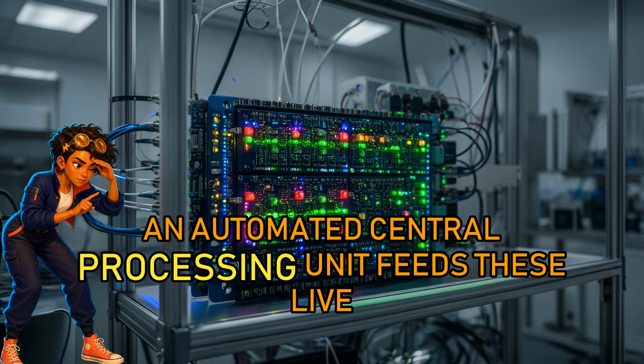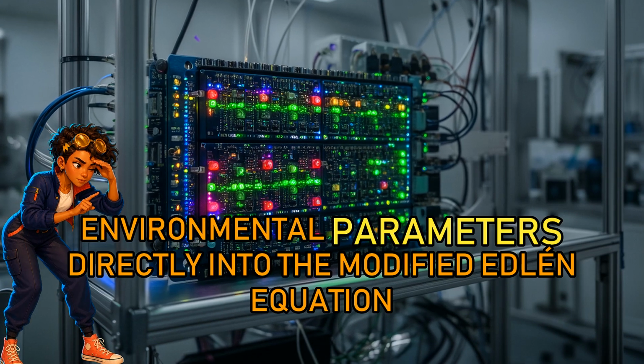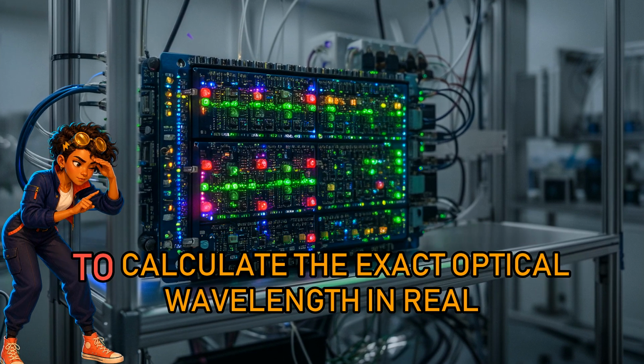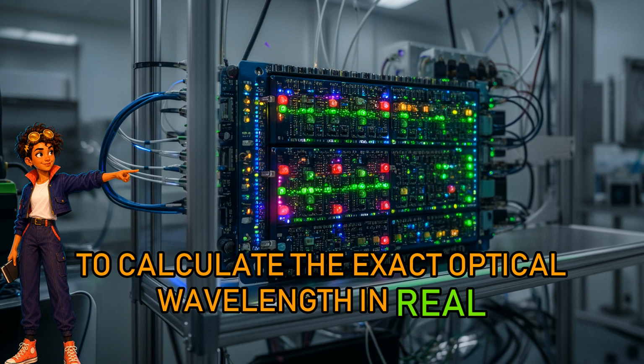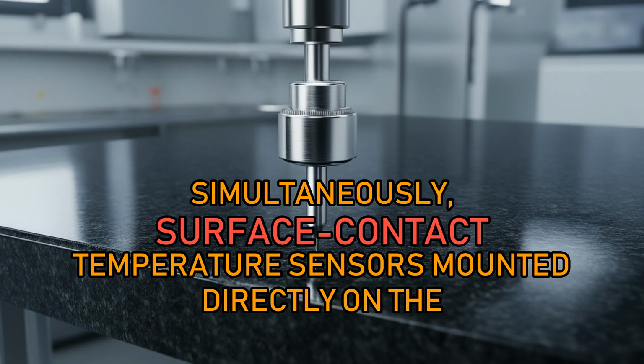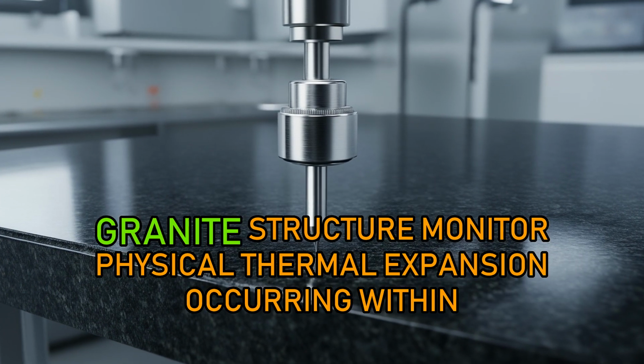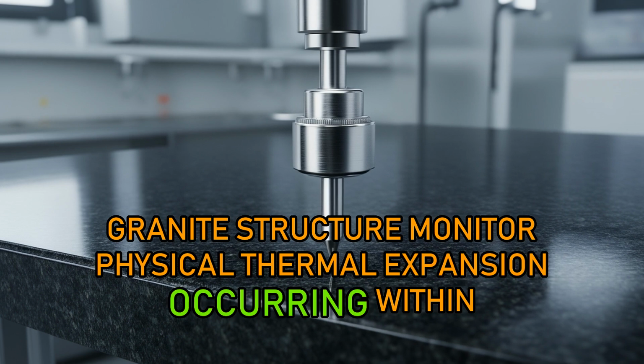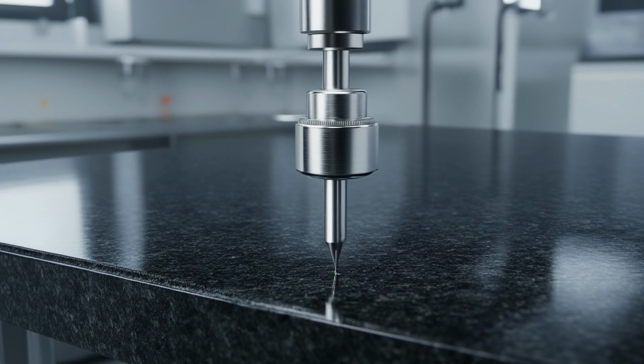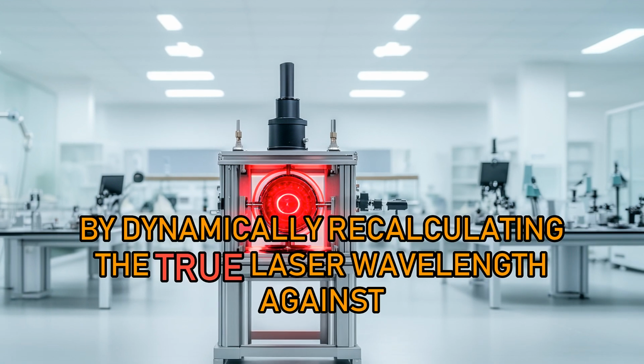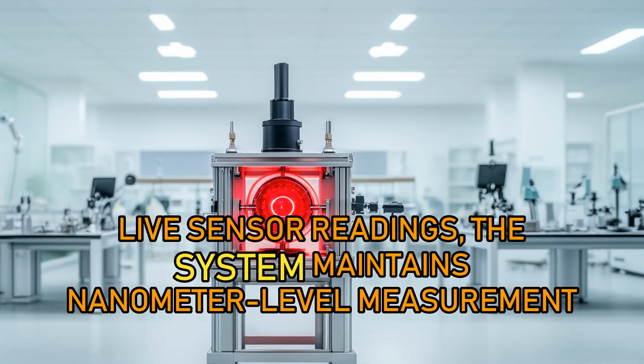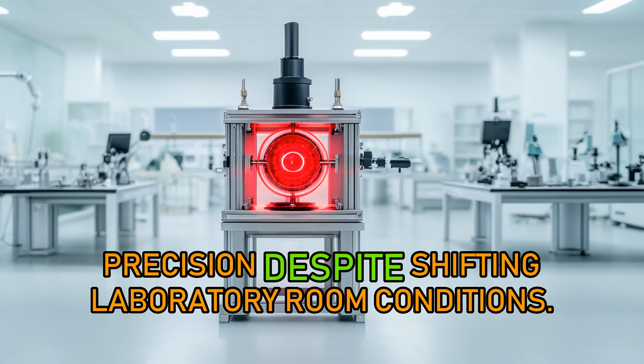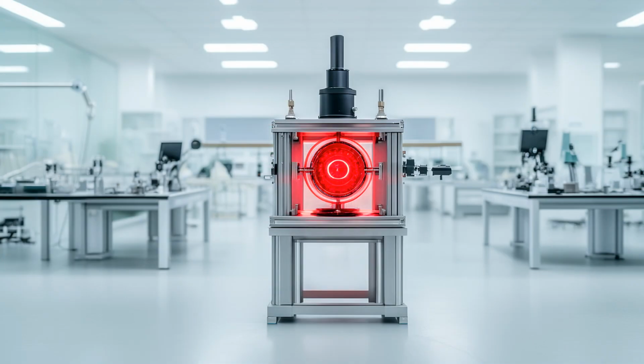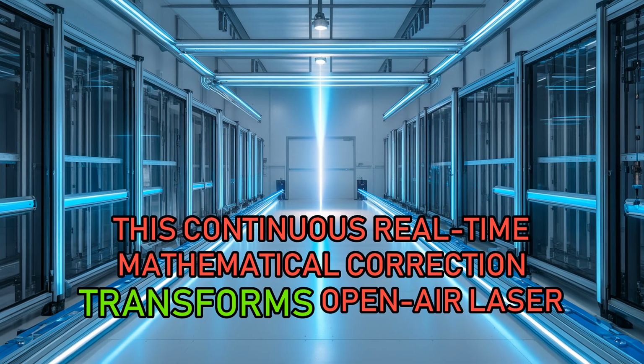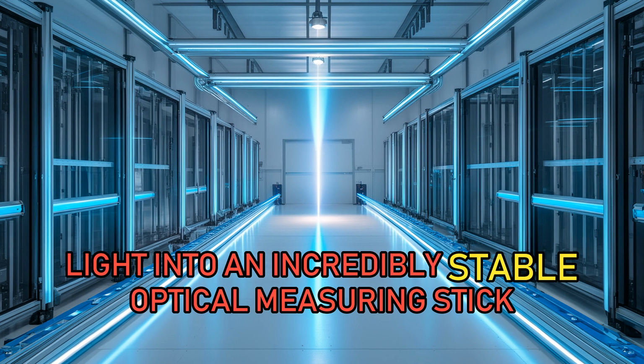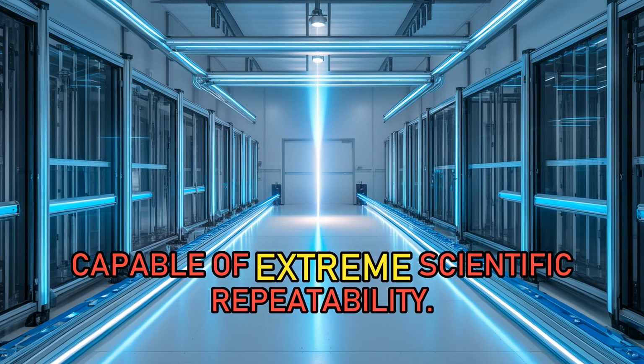An automated central processing unit feeds these live environmental parameters directly into the modified Edlen equation to calculate the exact optical wavelength in real time. Simultaneously, surface contact temperature sensors mounted directly on the granite structure monitor physical thermal expansion occurring within the mechanical bed and mounting fixtures. By dynamically recalculating the true laser wavelength against live sensor readings, the system maintains nanometer-level measurement precision despite shifting laboratory room conditions. This continuous real-time mathematical correction transforms open-air laser light into an incredibly stable optical measuring stick capable of extreme scientific repeatability.